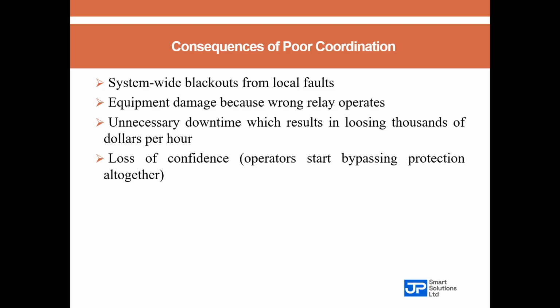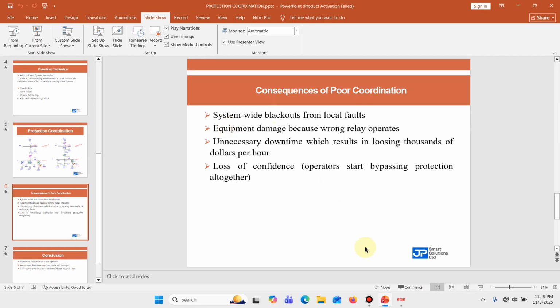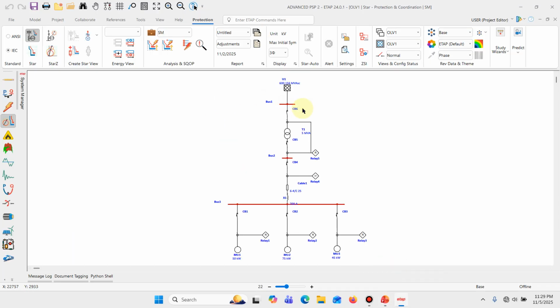Now, let me switch over to ETAP software and illustrate how the software makes protection coordination very easy. So I'll switch over to the software, and here we have a system. We have the power grid, then we have a bus bar, we have the breakers for the transformer. Here we have a differential protection scheme for this transformer. It's a 5 MVA transformer to a bus bar. So this transformer steps down the voltage for this section, and we have motor loads over here. We have our switchgears, we have our relays for each motor, we have a relay for this cable, we have a relay differential protection scheme for this transformer.